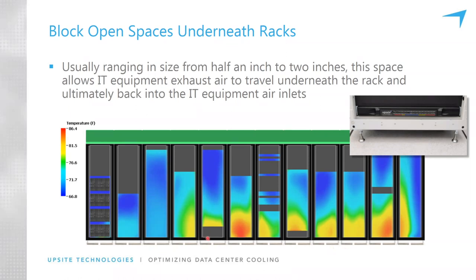I have also seen this numerous times in data centers that I've walked through, that the hottest spots are at the very bottoms of the cabinets. And this problem cannot be remediated or fixed by adding larger supply openings, like grills, or colder air. You can't get rid of it. And ironically, sometimes that actually makes it worse, because the high velocity air coming out of a high flow tile can create a lower pressure, drawing more hot air underneath the cabinet.